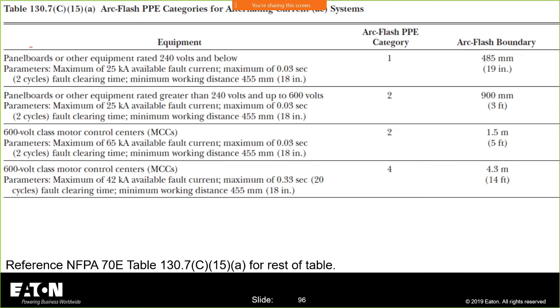But to say, I am following 70E here. I'm going to estimate my available fault current at that panel board, as long as it's less than or equal to 25,000 amps. I'm also going to look at what's the maximum clearing time? 0.03 seconds, and I'll tell you how they use it.